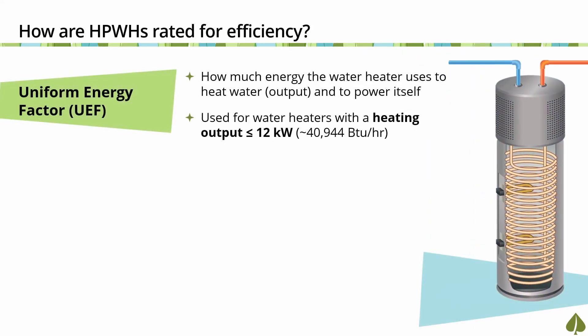There are two primary metrics for determining the energy efficiency of a heat pump water heater. The first metric is Uniform Energy Factor, or UEF. UEF is a measure of a water heater's energy efficiency and indicates how much energy the water heater uses to heat water, which is called the electrical output, and the energy to power itself. UEF is the metric used for water heaters with a heating output less than 12 kW, or less than 12,000 watts, roughly equivalent to 40,944 BTUs per hour. The higher the UEF, the more efficient the unit.